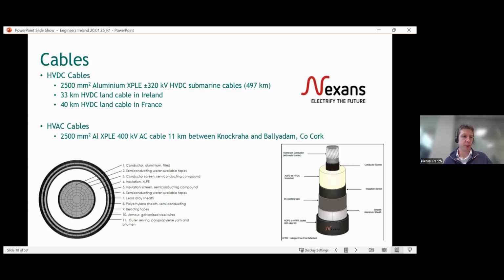To give a brief overview of the electrical cables that are going to be installed, we have AC and DC cables here. Starting with the DC cables, they are 2500 square millimeter aluminium XLPE cables, cross-linked polyethylene. The DC voltage level is plus minus 320 kV, so positive 320, negative 320. The submarine cable is 497 kilometers.